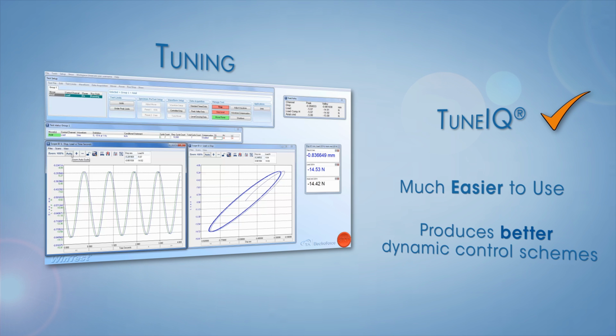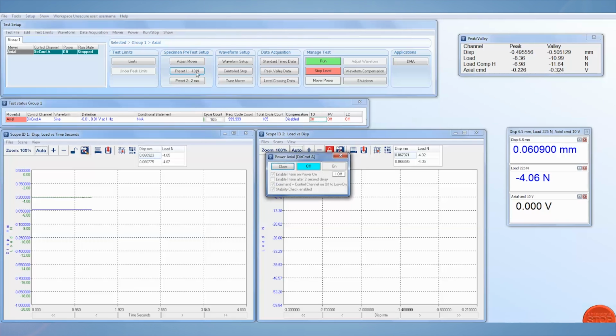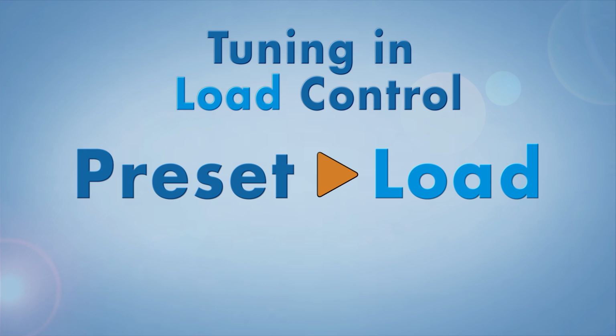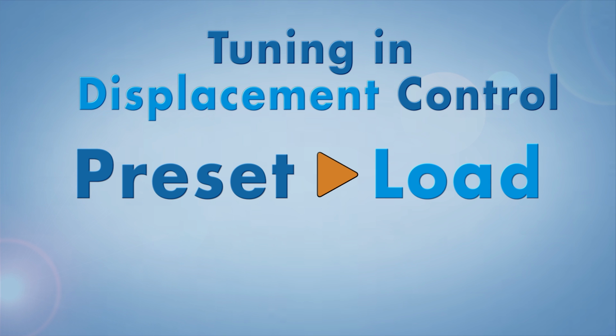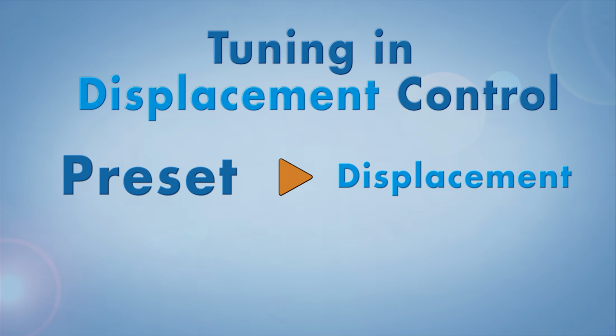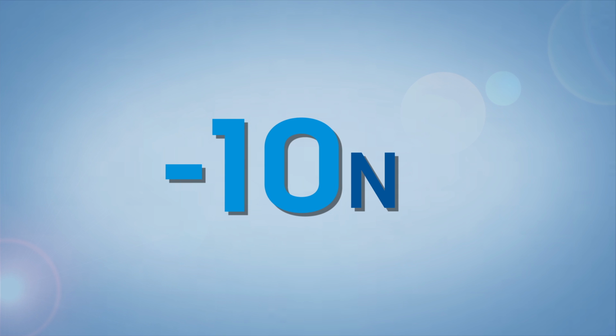doing manual tuning. Prior to tuning, you should preload or preset your sample so that you're at your mean level position. So if you're tuning in load control, you'll want to do a preset in load to get to your mean level in load. If you're doing displacement control, you want a preset to displacement to get you at your mean displacement level. For this test, I'm setting a preset to negative 10 newtons since I want to tune from negative 5 to negative 15 newtons in compression.